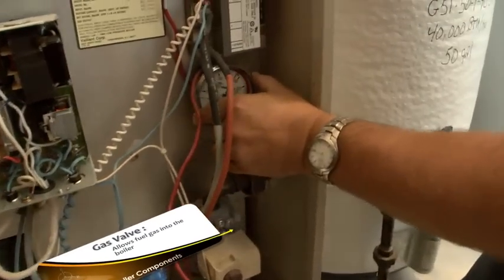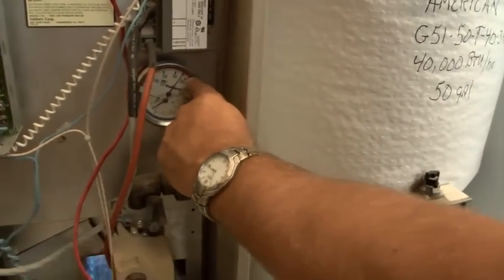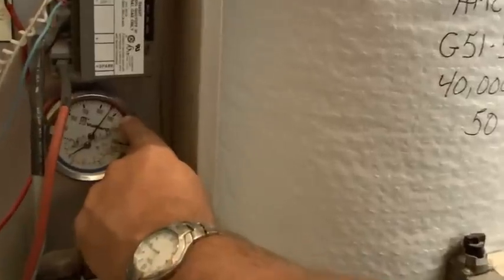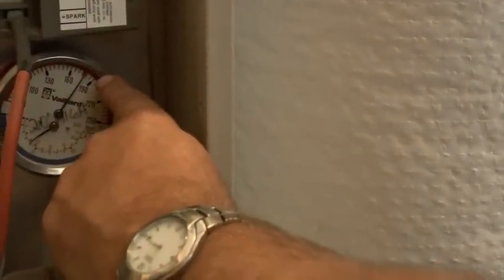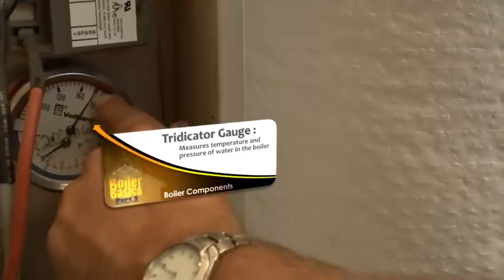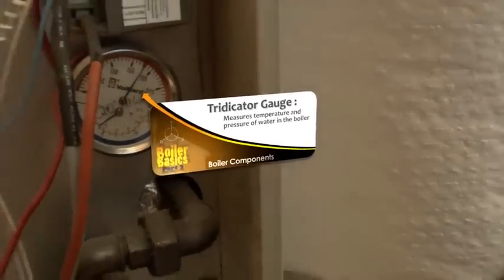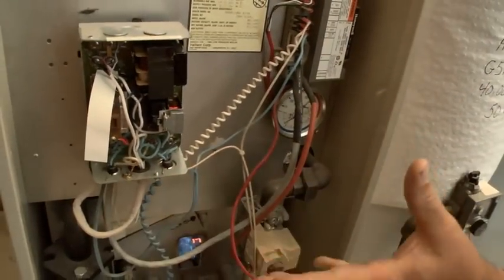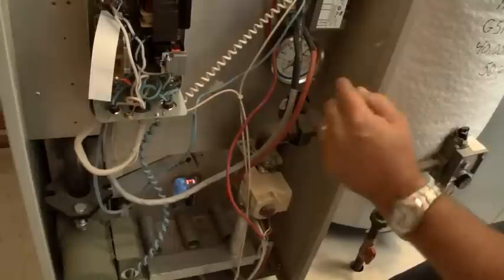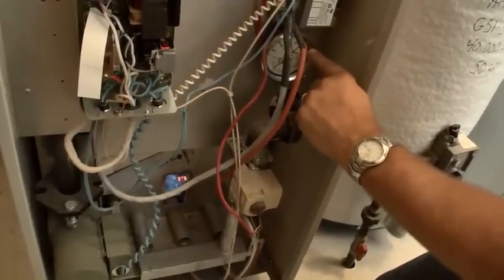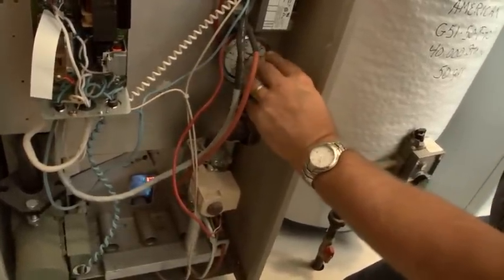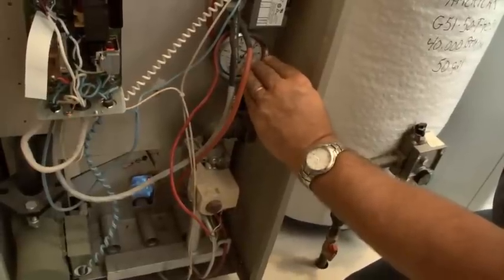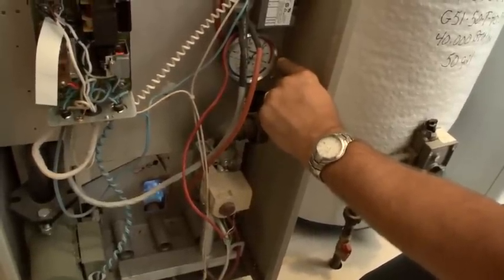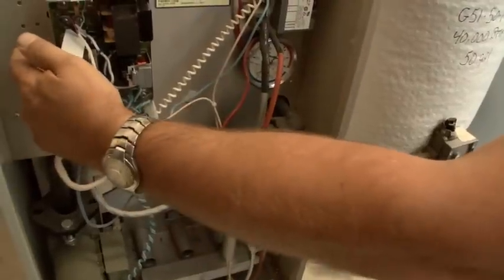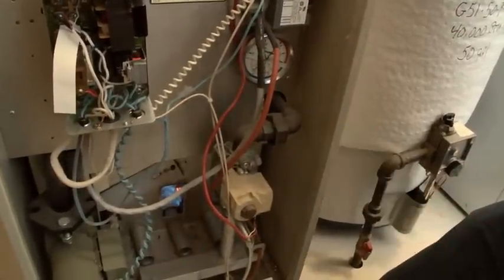And then over here we have, this is called a tridicator gauge. Right now the boiler temperature is a little over 180 degrees, and what we want to watch and see is what temperature does the flame shut off. Okay, and that is supposed to match this. Now there's always a little bit of a difference between the two, but we just want to make sure we're not too high on this. We really want the boiler shut off around 180, and if it shuts off a lot higher, we can adjust this over here and get it to shut off at a lower temp.